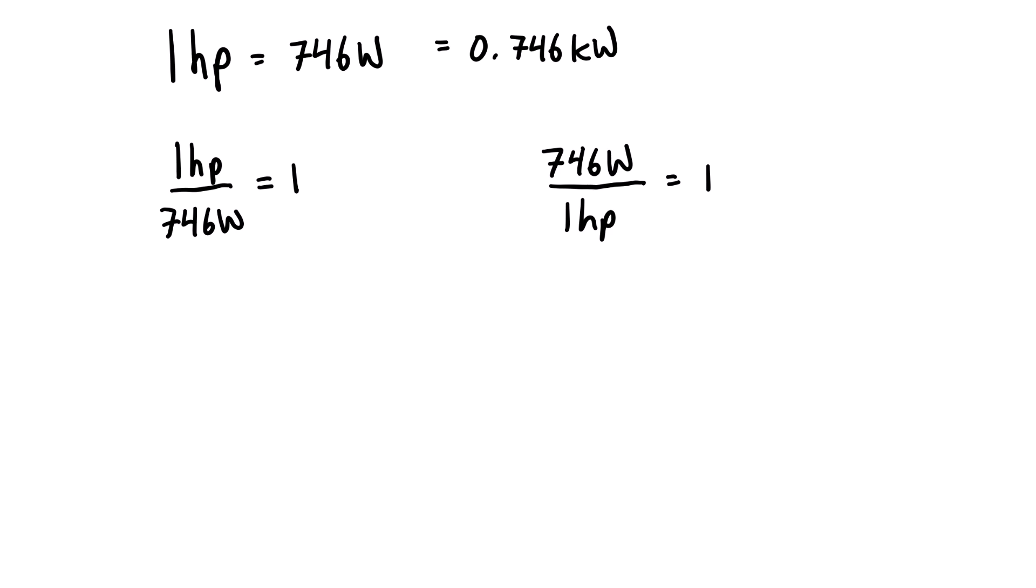For example, if we have, let's say, a 5 horsepower motor and we want to figure out how many watts or kilowatts it is, we'll just multiply it by unity. We're going to pick the one that has horsepower on the bottom so our units are going to cancel.